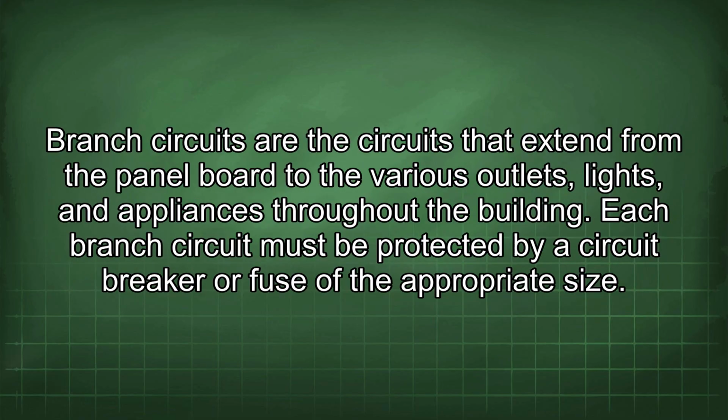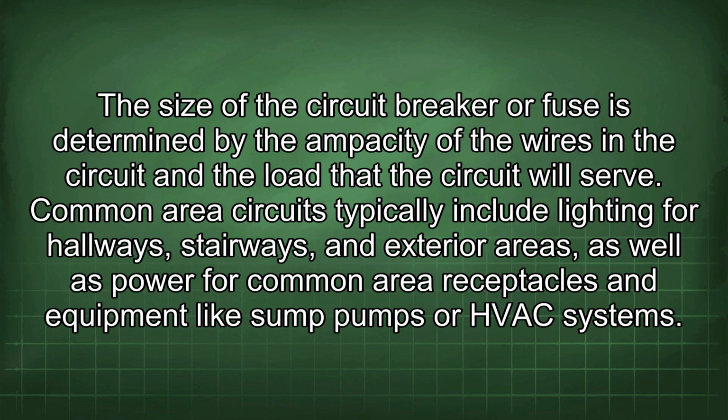Branch circuits are the circuits that extend from the panel board to the various outlets, lights, and appliances throughout the building. Each branch circuit must be protected by a circuit breaker or fuse of the appropriate size. The size of the circuit breaker or fuse is determined by the ampacity of the wires in the circuit and the load that the circuit will serve.